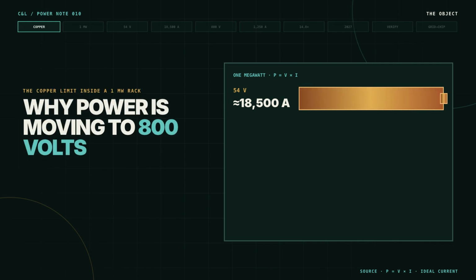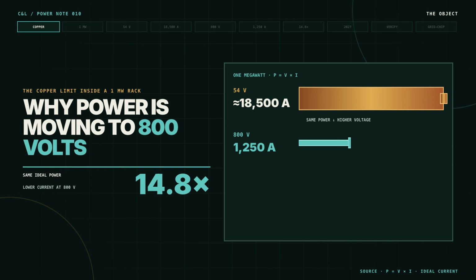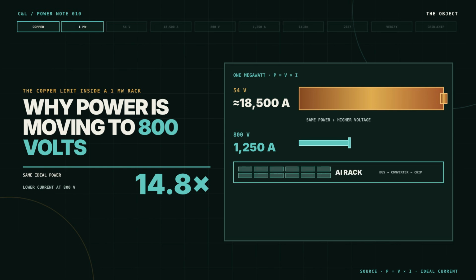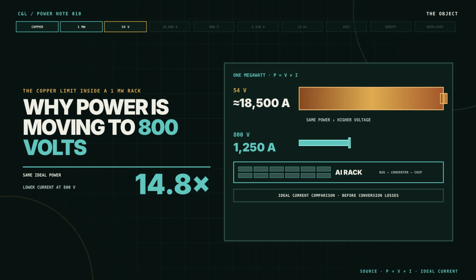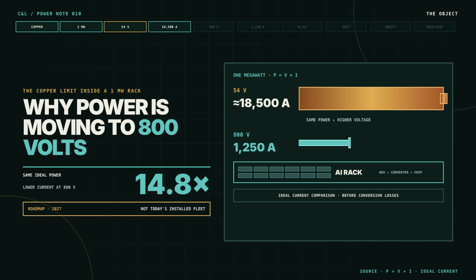This copper bus bar is the problem. 1 megawatt at 54 volts means roughly 18,500 amps. At 800 volts, the same ideal calculation is 1,250 amps. That 14.8 times current gap is why future AI rack power is being redesigned. But 800-volt direct current is not already standard across every data center. NVIDIA describes a transition for 1 megawatt racks and beyond, starting in 2027.